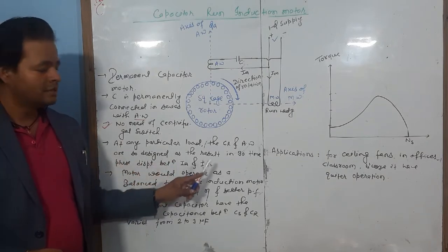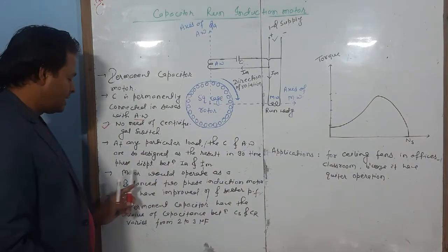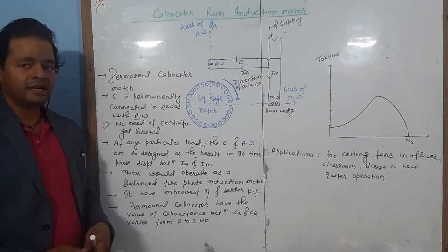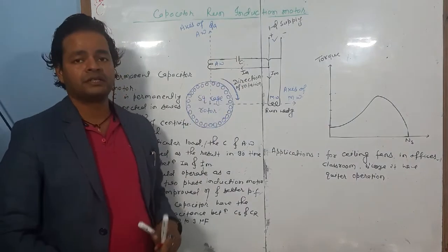At any particular load, the capacitor and auxiliary winding are designed to result in 90-degree time phase displacement between Ia and Im. In this case, the starting torque is mainly due to the auxiliary winding.